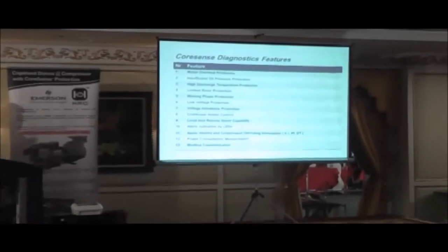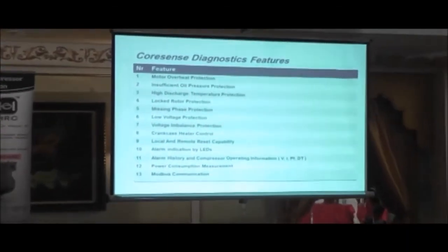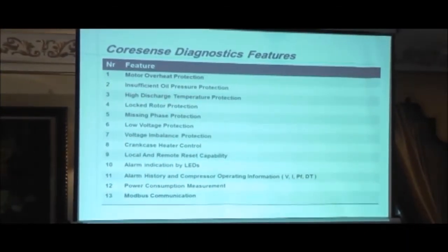The diagnostic module also has communication capability. So you can connect this compressor in a network either to a rack controller, or if you've got a standalone application, you can connect it to your PC and you can upload the values from the compressor. So you will be able to see how the compressor has been performing. So those are some of the main features.